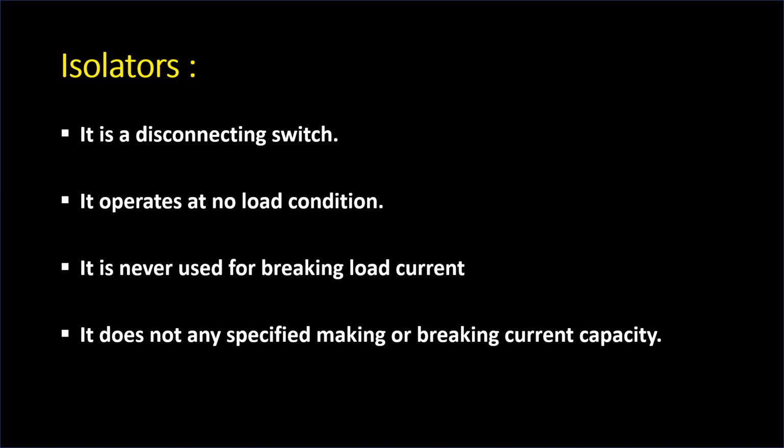It is never used for breaking load current like an ordinary switch. Whatever type of switches we are using in electric power system, its purpose is making and breaking the system, and we always operate it at load condition. But your isolator is never used for breaking load current, and as I am saying here, it is not operated at load condition, so there is no need to specify making and breaking current capacity for isolator.